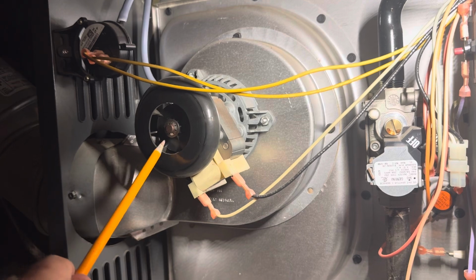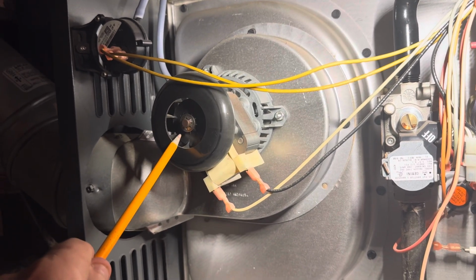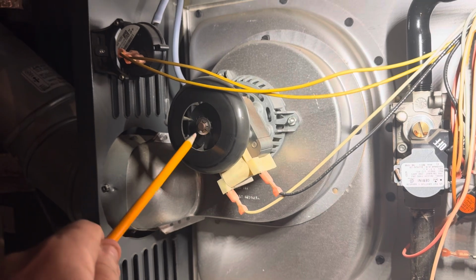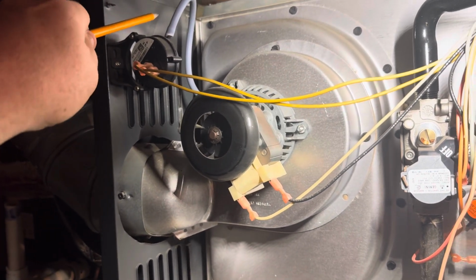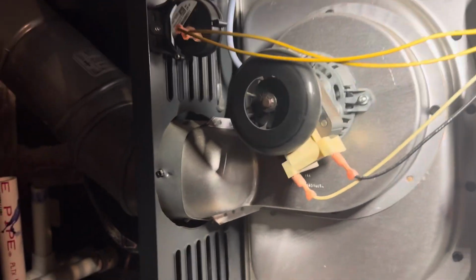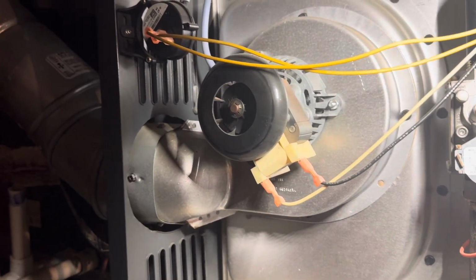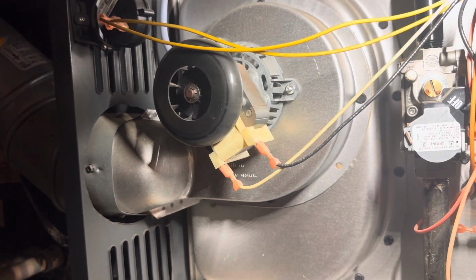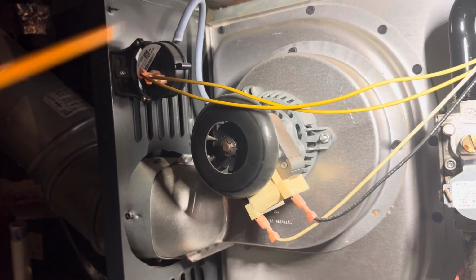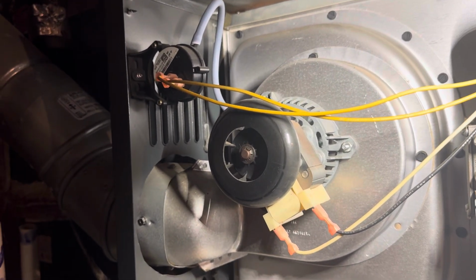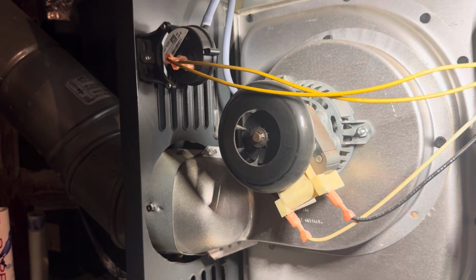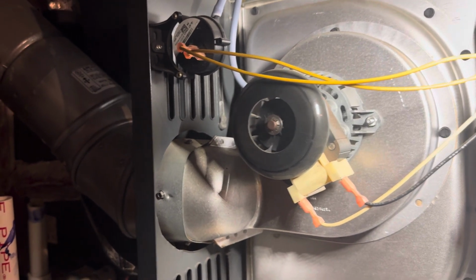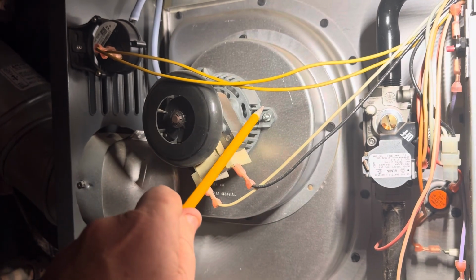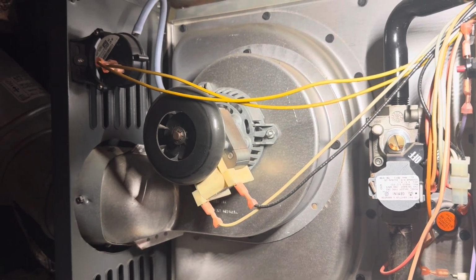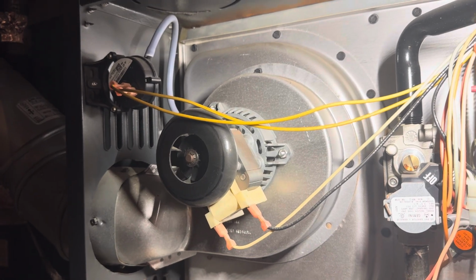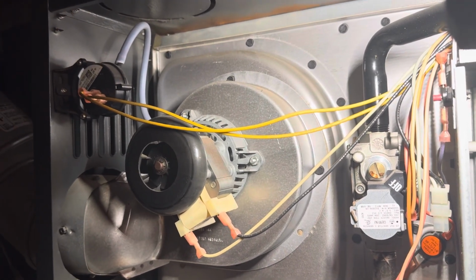We have a safety to know that the inducer is on and it's not blocked in the flue pipe. And that's up here, the pressure switch. So, for example, if there was a bird nest or something that were to block the flue pipe, the pressure switch up here would not close and it would not allow the furnace to operate. Similarly, if this motor was bad, the same thing. The furnace would not start. So that's a safety feature in the pressure switch.